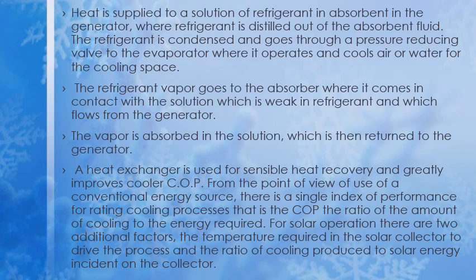A heat exchanger is used for sensible heat recovery and greatly improves cooler COP from the point of view of use of a conventional energy source. There is a single index of performance for rating cooling processes, that is the COP, the ratio of the amount of cooling to the energy required. For solar operation, there are two additional factors: the temperature required in the solar collector to drive the process and the ratio of cooling produced to solar energy incident on the collector. These are the main steps from the previous slide to this slide, and we are going to see the further working and how it happens.